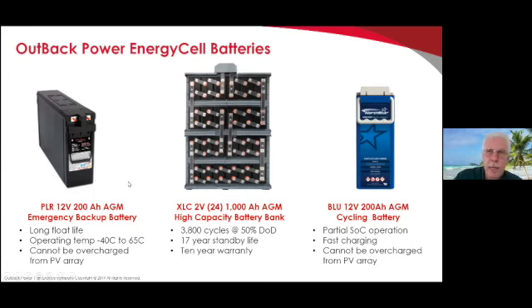That's one of the things we've seen sometimes in emergency backup power situations — people want to go big on solar, net meter a lot of that energy, and offset their utility bill. Batteries are kind of expensive, so they might only have 2 strings of batteries for emergency backup, but with a big array on a regular AGM battery, it's conceivable you could exceed the recommended charging current. That's not an issue with this battery or the Blue battery, so they're really unique in that regard.